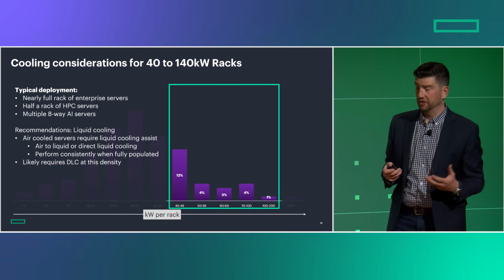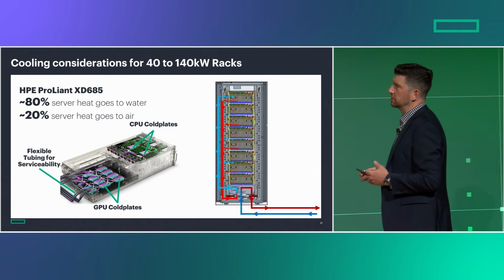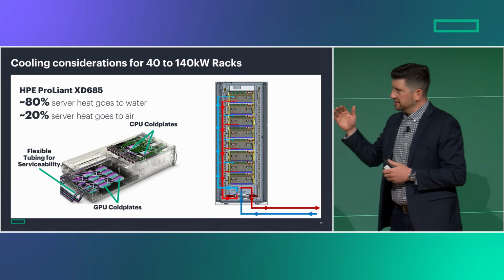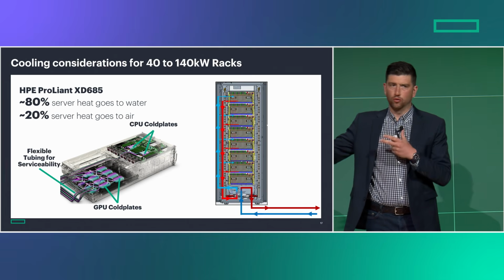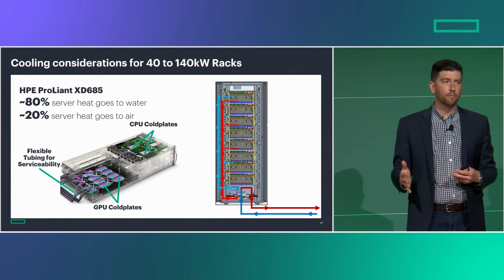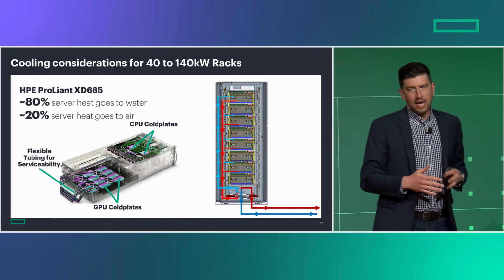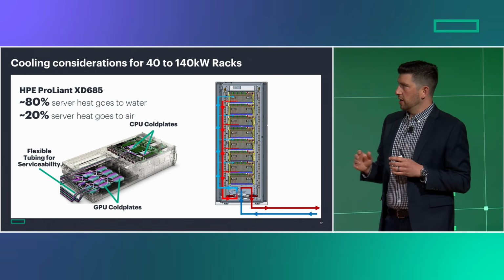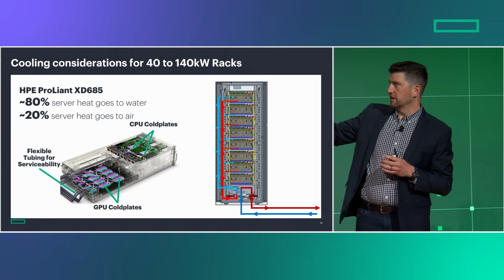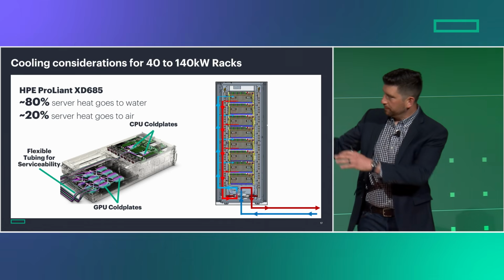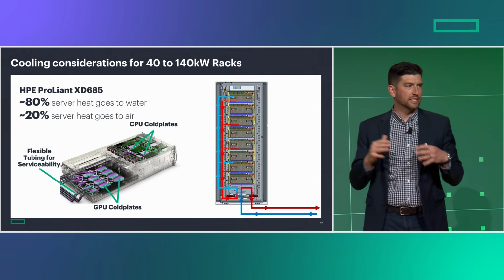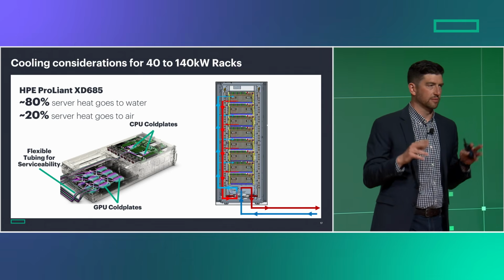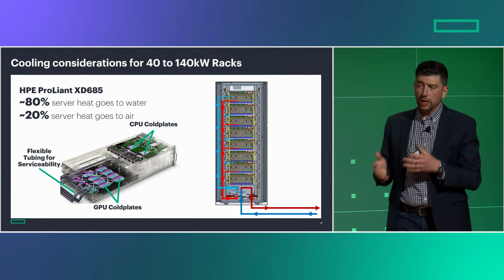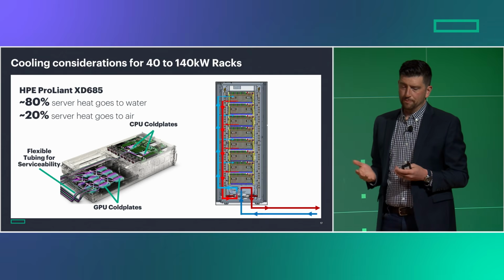So what does this stuff look like, the real nuts and bolts? Well, in almost all cases, we're going to have cold plates sitting directly on top of the CPU or GPU, pumping that heat away. The numbers really vary, so I always put an approximate symbol here, but in general about 80% of this server heat ends up getting captured by the DLC system, the direct liquid cooling, and 20% still needs ambient air cooling.